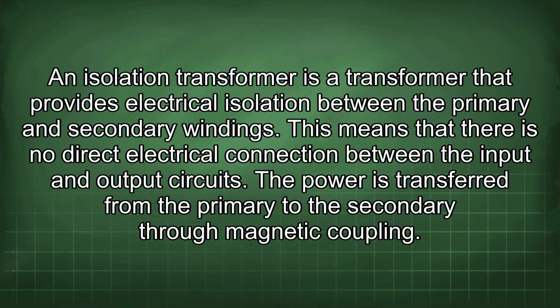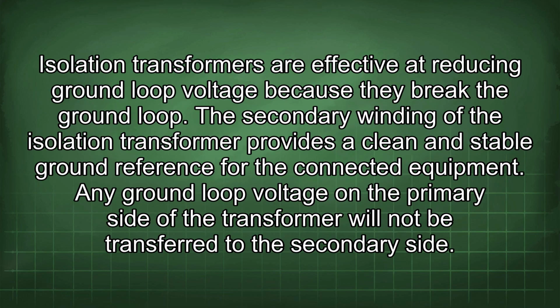An isolation transformer is a transformer that provides electrical isolation between the primary and secondary windings. This means that there is no direct electrical connection between the input and output circuits. The power is transferred from the primary to the secondary through magnetic coupling. Isolation transformers are effective at reducing ground loop voltage because they break the ground loop. The secondary winding of the isolation transformer provides a clean and stable ground reference for the connected equipment. Any ground loop voltage on the primary side of the transformer will not be transferred to the secondary side.